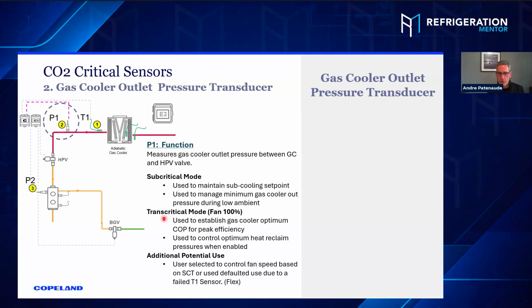In transcritical mode, that pressure transducer is used when the fans are running full speed and we're trying to establish an optimum COP point. The high pressure valve is moving and that pressure transducer is measuring that. Even in heat reclaim mode, it's used to modify that. So even in the winter, we might be pushing it in transcritical mode. And again, it's measuring and adapting and providing the information for the high pressure valve positioning.